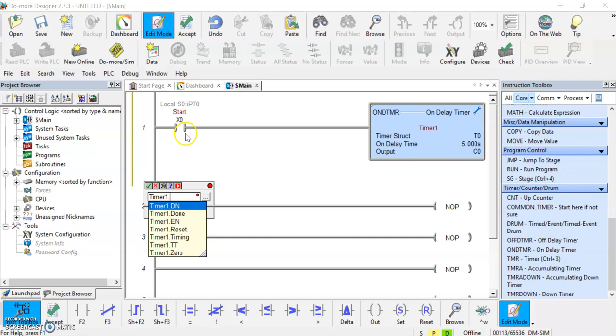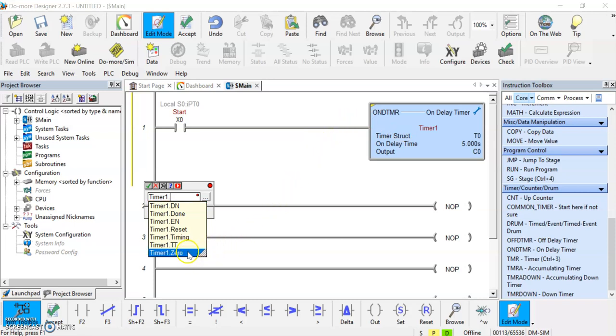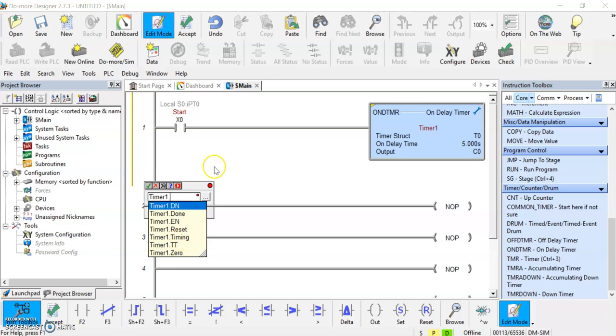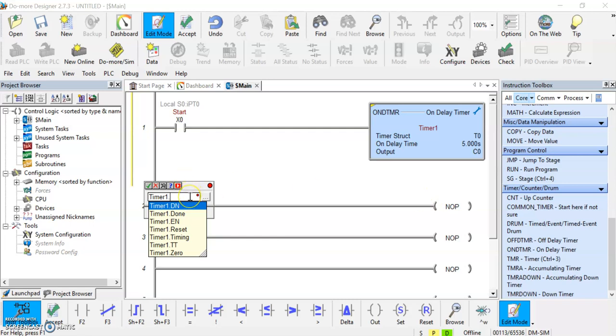So as long as this is true, this timer is enabled. So there may be a reason to use that if that's what you want to do. But that's what that would do. The other one that's interesting is the timer timing or TT, which is again the same thing here. When we select that, when this rung goes true, this bit down here will also go true for the five seconds that it starts timing. But then after that, it'll go off. It'll go back to a zero state. So it'll be a one or active only for that five seconds.